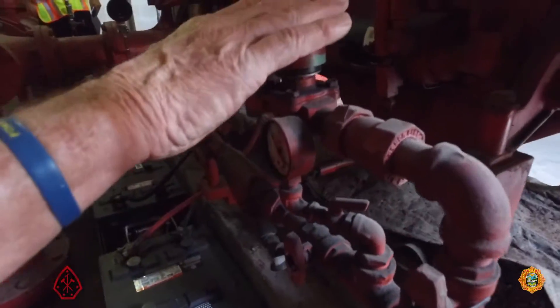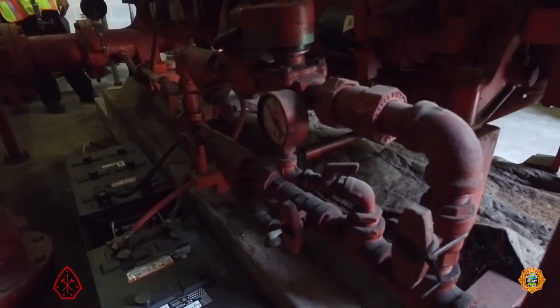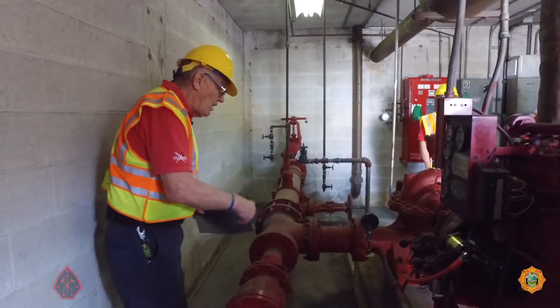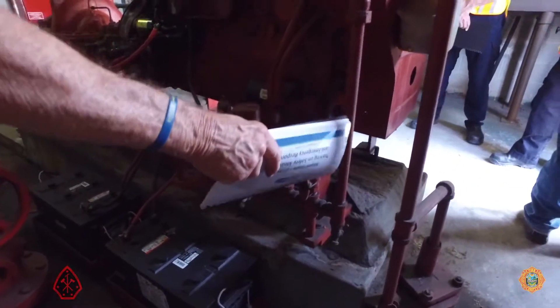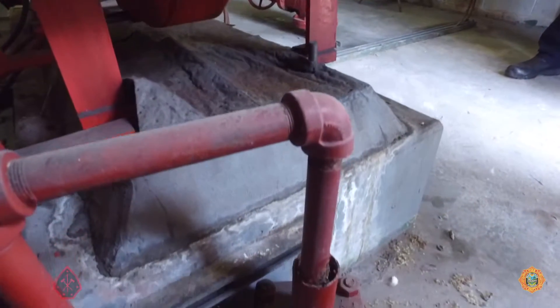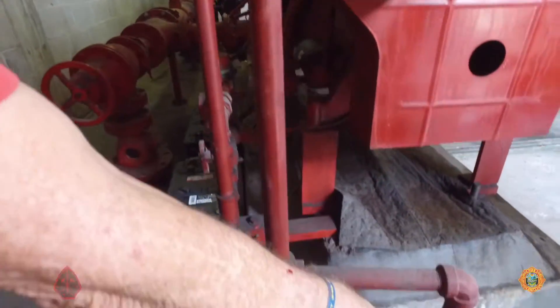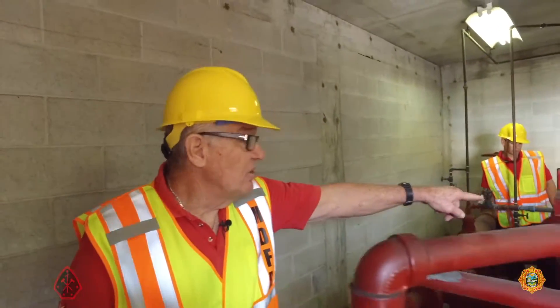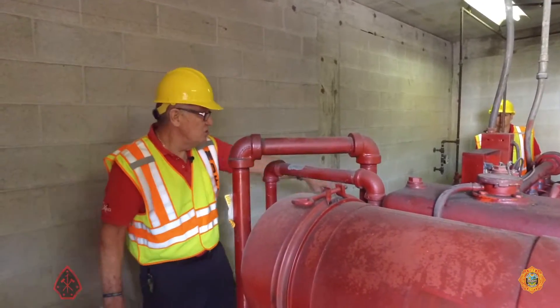If you didn't see water coming out of the drain for the heat exchanger, turn the secondary one up. The diesel engine is going to run at about 180 degrees of water coolant temperature. The water comes from the discharge side of the pump through the cooling lines up to the heat exchanger. The coolant doesn't intermingle with the water — it has coils in the heat exchanger. It comes out and by design drains, so you have a constant circulation. If you shut off the water to this pump with the pump still running, you will burn up the diesel engine and you will burn up that fire pump.